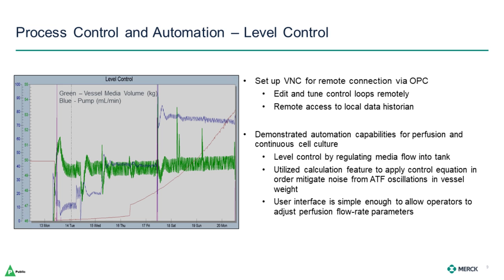Now let's look at our experiences with process control and automation during the evaluation. The demo unit came with a G3Lab controller with Finesse TruBio DeltaV. Without any customization before arrival, we were able to set up the bioreactor for remote connection via OPC. This was important to us as it enabled the editing and tuning of control loops remotely, as well as access to the local Delta V historian trends. The focus here is on the green trend, which is the vessel weight oscillating rapidly due to the alternating flow of the ATF controller, and the blue trend, which is the media in-pump for our perfusion media. This is a visual representation demonstrating some of the automation capabilities for perfusion and continuous culture, in this example showing level control by regulating media flow into the tank.